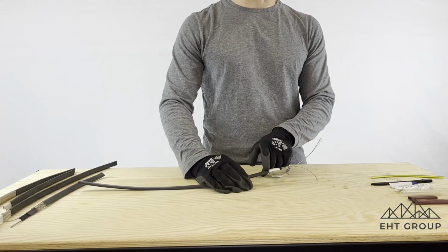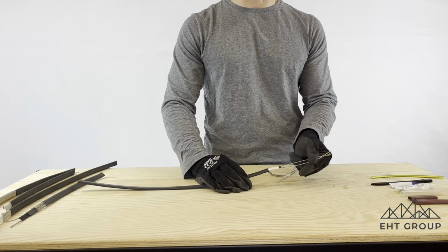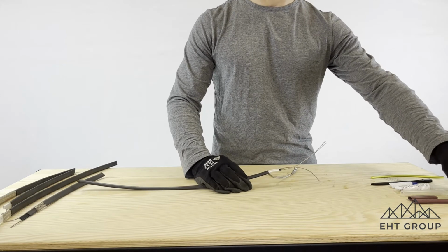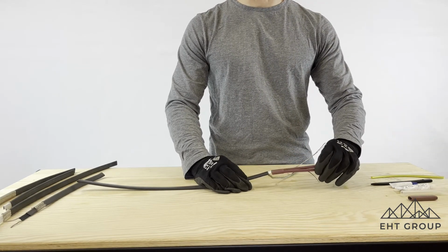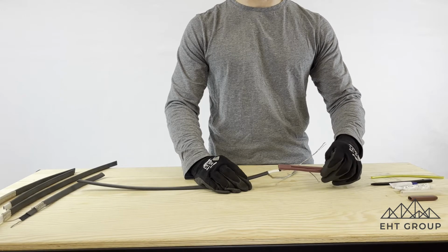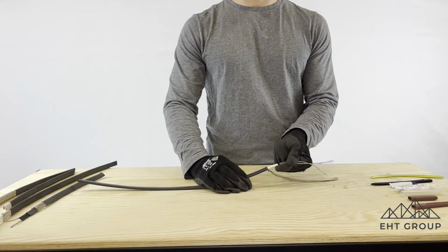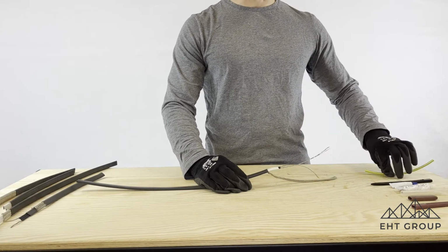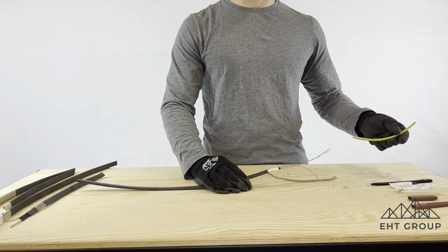We're also making sure that we don't see any cuts or any nicks into this inner insulation. Next, we're leaving a spacing of the inner insulation, and then we're cutting back our semiconductive core. And typically what will happen here, depending on the manufacturer's cable, is that these sort of boots will get put on, and then there'll be a compound that'll get installed in those boots as well. And then the braid is typically going to go into a specific sheath as well for our power terminations.